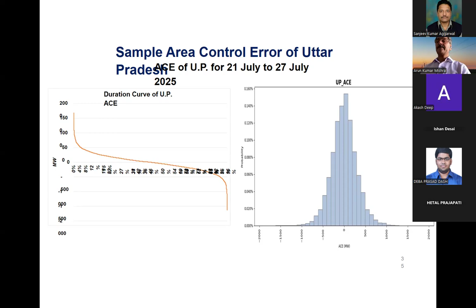This is a sample area control error of Uttar Pradesh, showing how we arrived at the requirement of 800-odd megawatt for reserve. This picture shows whether we are operating balanced. If there's more to the left, area control is over-generation, so we can be more aggressive. If there's more to the right, we can shift our operating points so we are less dependent on and less of a burden on the region - that's the kind of insight generated from the overall analysis.